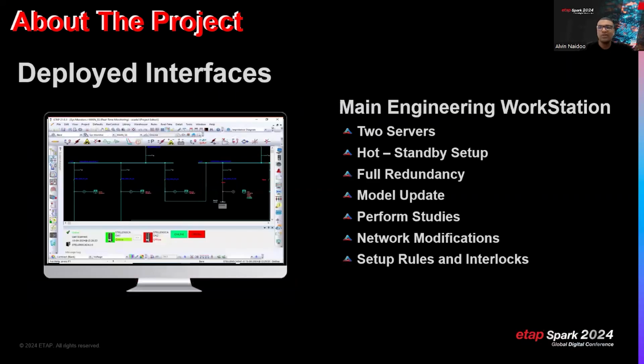Thereafter, the deployed interfaces were as follows. Directly feeding from the RTUs through the master stations were connected the engineering workstations. These were a 2-server setup with a hot standby with full redundancy between them. So should the primary server fail, there'll be a seamless changeover and integration of the hot standby. At the main engineering workstation, model updates could be performed, studies could be undertaken, network modifications, rules and interlocks could also be set up, as well as your mobile switching and your monitoring of the network.